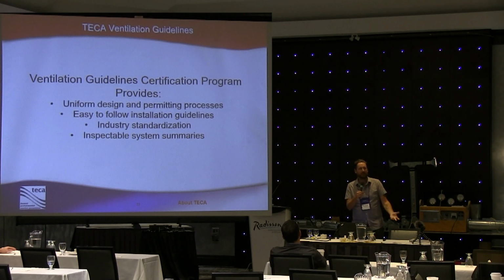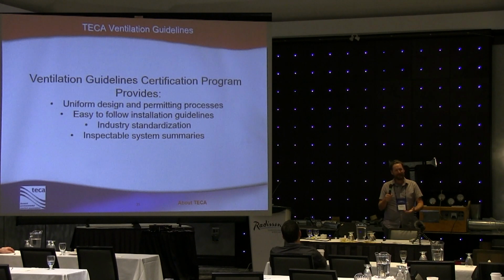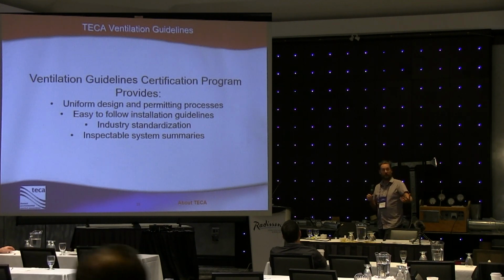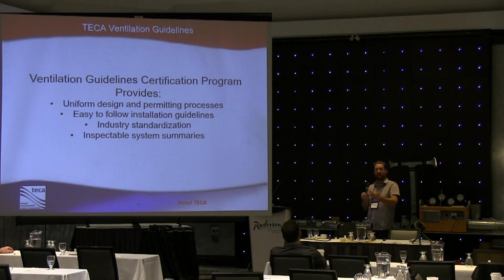And it's like, well, it was a good deal. Well, it's a good deal, but we've got some other issues to deal with now. Namely, are we going to create a negative pressure situation? Are we going to start exhausting out of that building so much that we're going to have air rushing back in wherever it can? And if we've got those naturally aspirated or thermally buoyant appliances, are we going to have a problem with that, right? And that's the big kicker for sure.